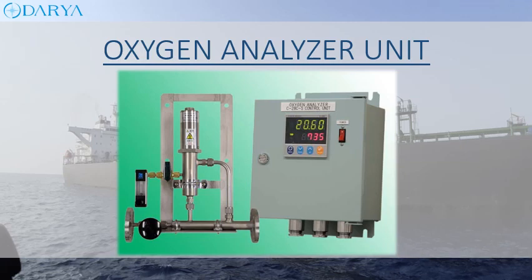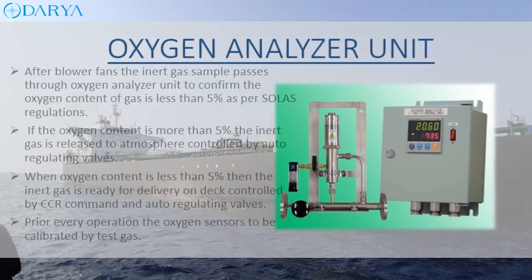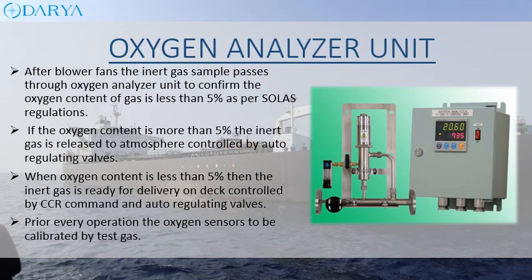After the blower fans, the inert gas sample passes through the oxygen analyzer unit to confirm the oxygen content of the gas is less than 5% as per SOLAS regulations. If the oxygen content is more than 5%, the inert gas is released to atmosphere, controlled by auto-regulating valves. When oxygen content is less than 5%, the inert gas is ready for delivery on deck, controlled by CCR command and auto-regulating valves. Prior to every operation, the oxygen sensors are to be calibrated by test gas.